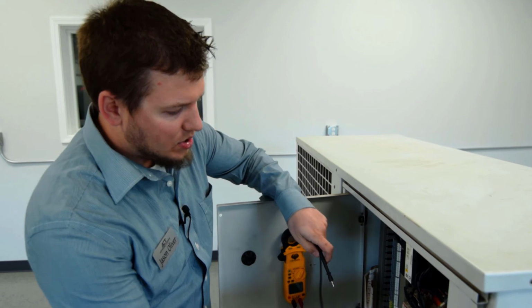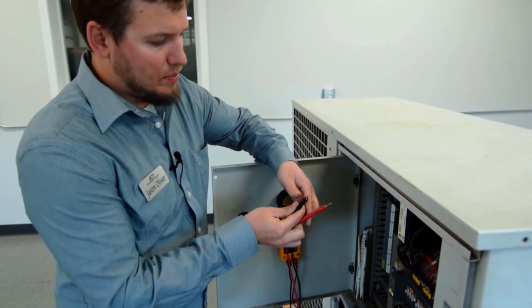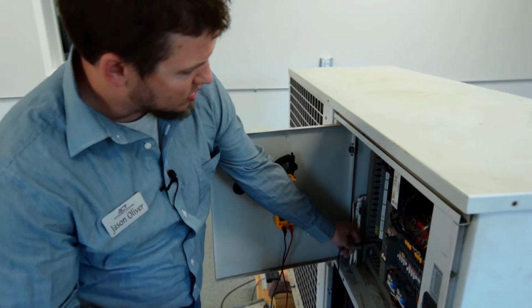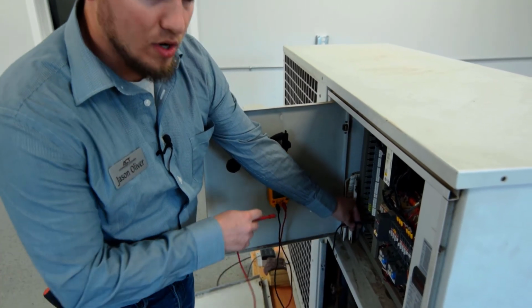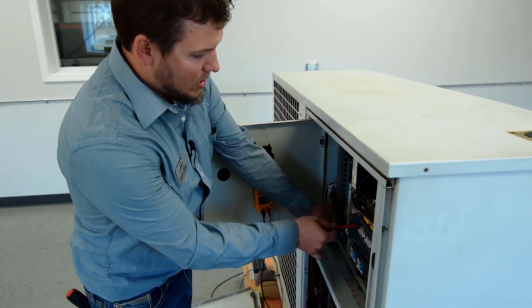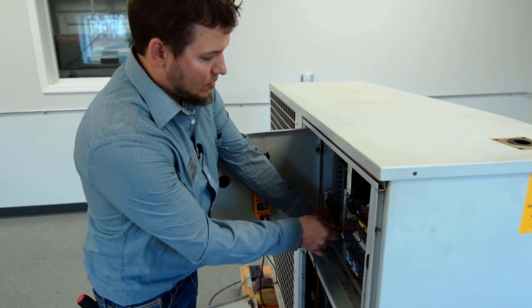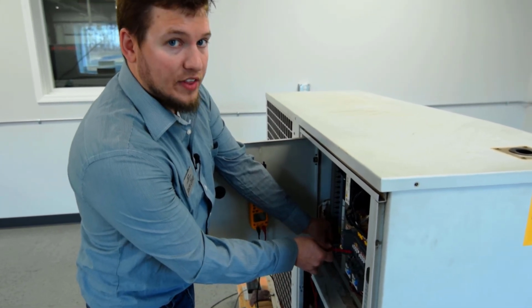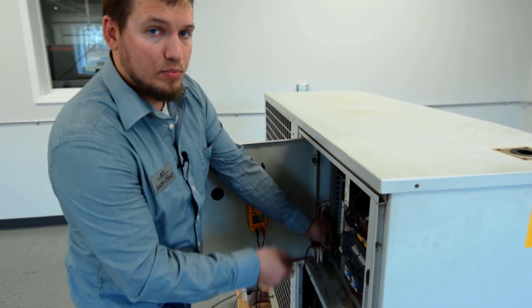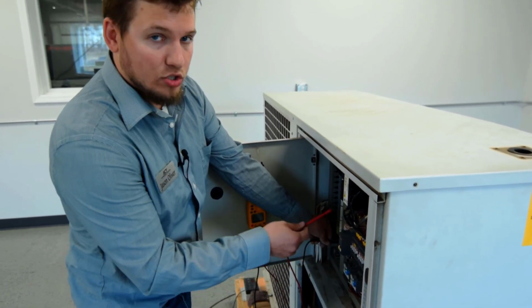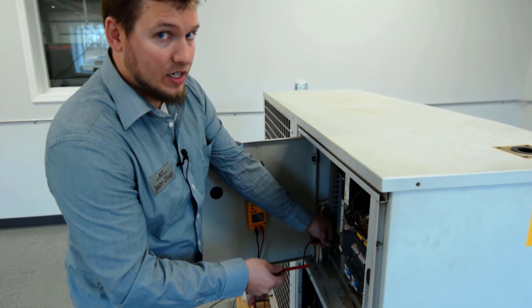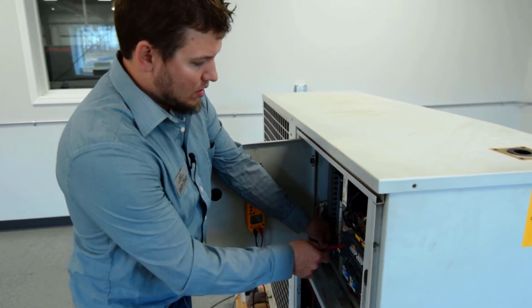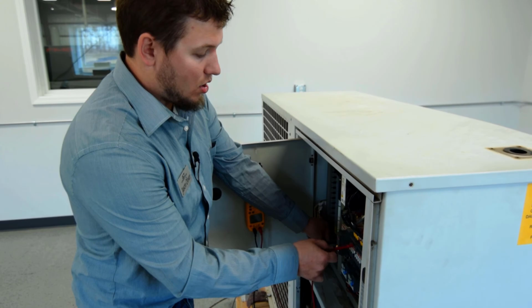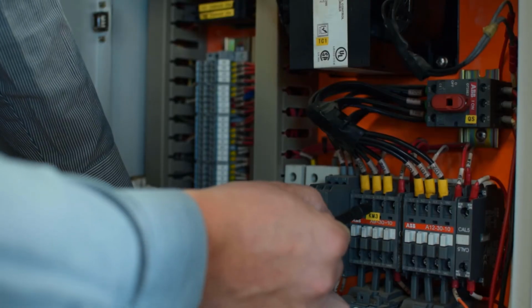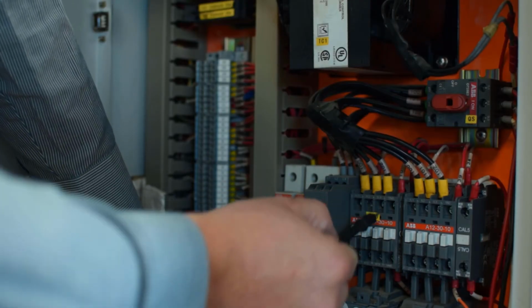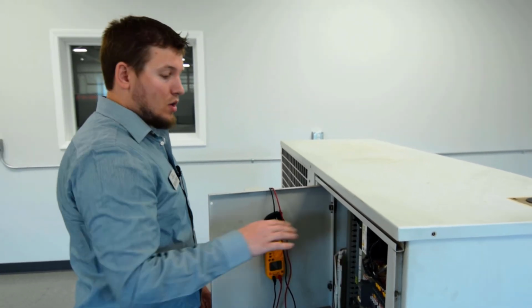So once you have power to the chiller and the contactor for the pump is running, what you're going to want to do is go to ground on one of your legs, make sure your voltage meter is on volts, and measure the voltage going into the contactor. And then measure the voltage on the outlet of the contactor to see if there's any voltage drop. If you notice a voltage drop greater than 1 volt, please contact ACT immediately for more troubleshooting. You're going to want to do this for all 3 legs on the compressor on both contactors. Once you've verified there's no voltage drop between the contactors, we can go ahead and move on to the next step.